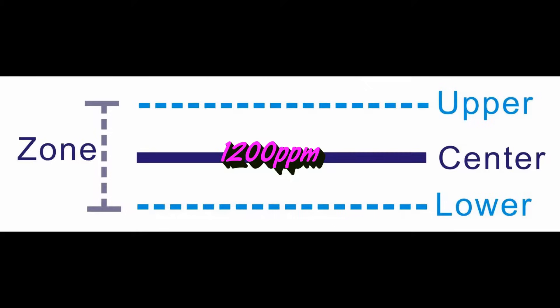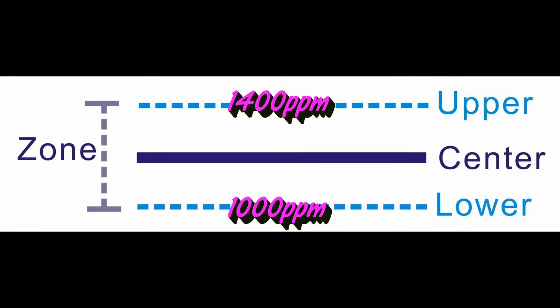For example, while the center is 1,200 ppm, zone is 400 ppm, this means the controlling upper and lower limits are 1,400 and 1,000 ppm.